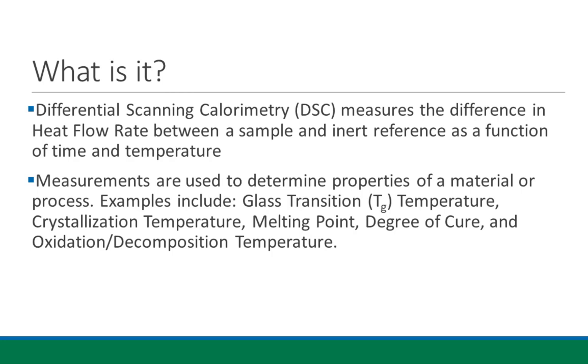With this technique we can determine several different properties of a material or a process taking place inside the system. Examples include glass transition, crystallization, and melting point temperatures. You can determine degree of cure, indicating if a sample is fully cured or not, and what percentage of cure it has. You can also determine oxidation or decomposition temperature, though we typically don't want to decompose samples inside the instrument as it might dirty the cell.